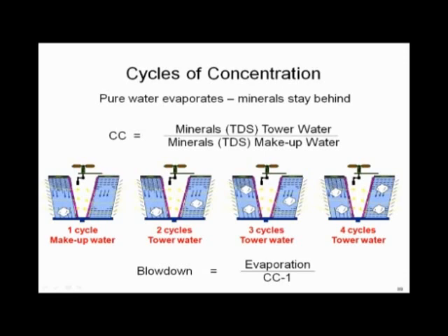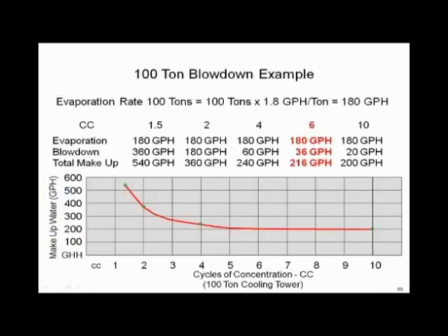I evaporate that 1,000 gallons again — my two rocks stay behind. Bring in another 1,000 gallons with another rock: three cycles of concentration, three rocks. Evaporate again — three rocks remain. Bring in another 1,000 gallons and now you've got four cycles of concentration, four rocks. Concentration is that simple. As you can see, if you don't have some makeup water management, you're going to wind up with a tower full of rocks. We've got to learn to deal with cycles of concentration.